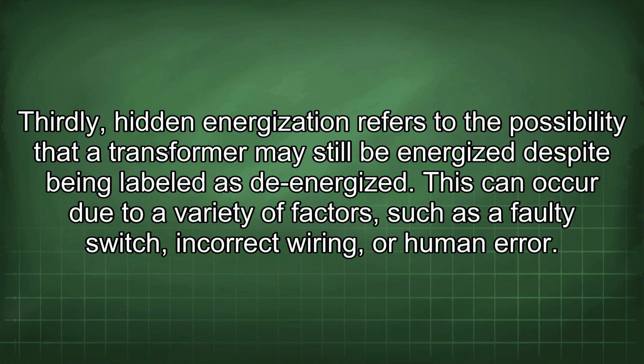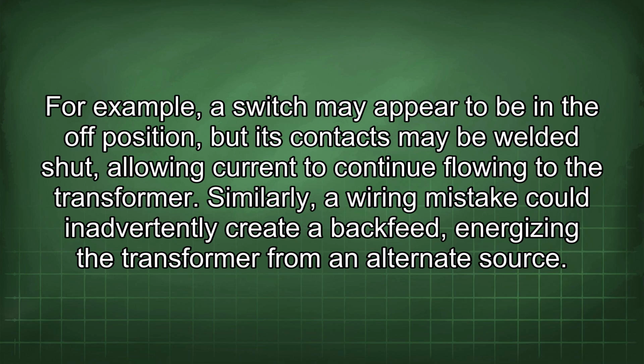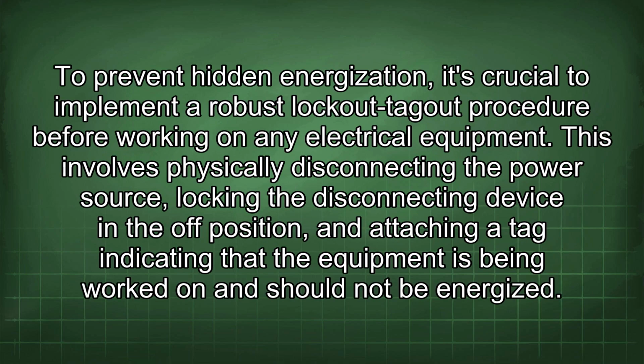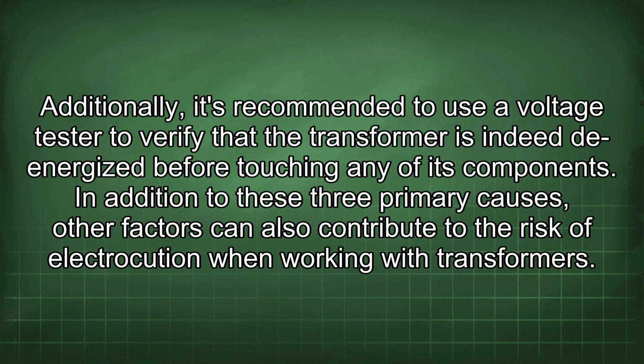Thirdly, hidden energization refers to the possibility that a transformer may still be energized despite being labeled as de-energized. This can occur due to a variety of factors, such as a faulty switch, incorrect wiring, or human error. For example, a switch may appear to be in the off position, but its contacts may be welded shut, allowing current to continue flowing to the transformer. Similarly, a wiring mistake could inadvertently create a backfeed, energizing the transformer from an alternate source. To prevent hidden energization, it's crucial to implement a robust lockout-tagout procedure before working on any electrical equipment. This involves physically disconnecting the power source, locking the disconnecting device in the off position, and attaching a tag indicating that the equipment is being worked on and should not be energized. Additionally, it's recommended to use a voltage tester to verify that the transformer is indeed de-energized before touching any of its components.